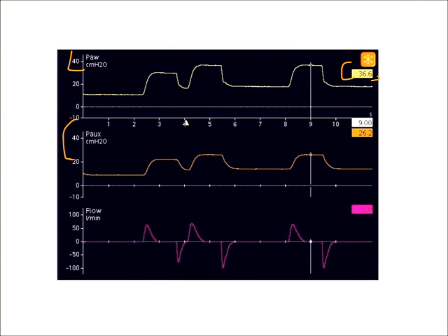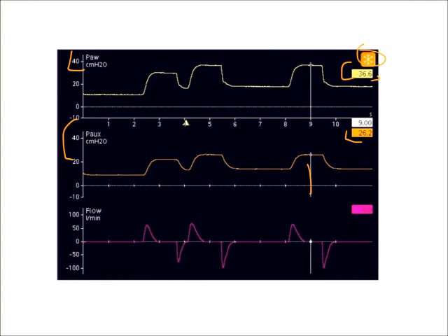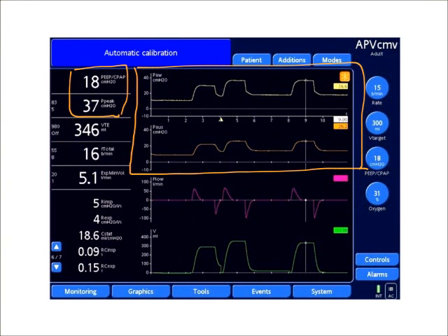These values here are actually the measured values based on the cursor. The screen was frozen and we used the control knob to scroll over to see the pressures.